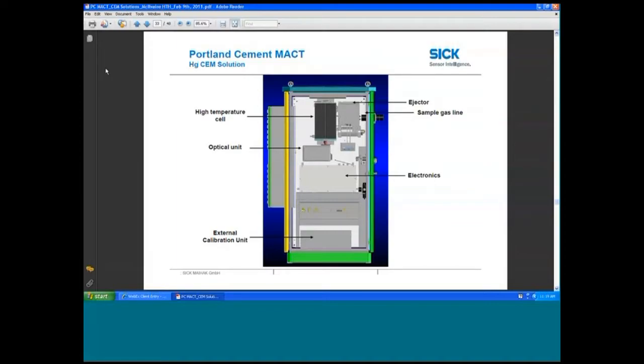We're using an ejector pump to pull the sample through. So that means we don't have any diaphragm pumps or anything to maintain. We simply use instrument air to pull a sample down the sample gas line and through the system. And from the sample gas line, we're injecting the gas straight into a high temperature cell. And in the cell, this is where we're doing our conversion.